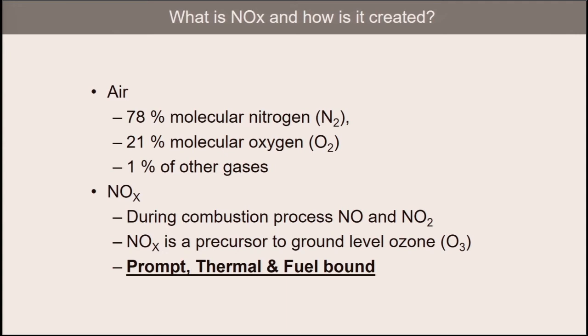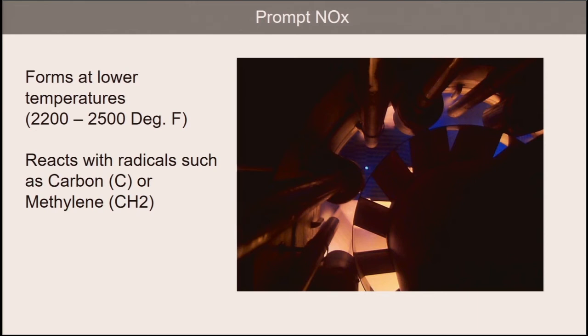Allow me to briefly describe them. With the exception of fuel-bound NOx — which we can't really do anything about except burn a synthetic fuel — we'll limit our discussion today to prompt and thermal NOx, beginning with prompt NOx. Prompt NOx is a pollutant which forms at the lower temperatures in the early stages of oxidation or combustion, reacting with radicals in the fuels such as carbon and/or methylene. It is a relatively small contributor to overall NOx production, but should certainly not be overlooked.